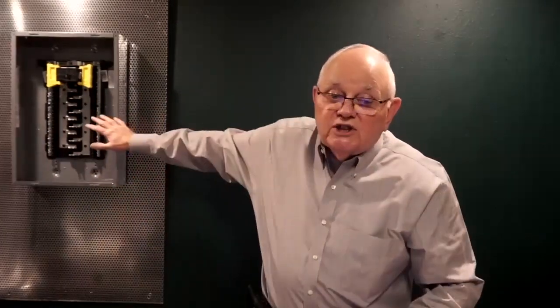If I enter that boundary, I'm subject to electric shock because I could reach in and touch something I shouldn't. And then as I get 1 foot away, that's considered to be the restricted approach boundary. And that's based on inadvertent movement primarily, the very small gap, like 30 thousandths of an inch, that an electric arc could possibly jump through the air at that low voltage level, plus my 1 foot of inadvertent movement adder, they call it, where I may be working in the panel and accidentally, look around and touch something I shouldn't or whatever.